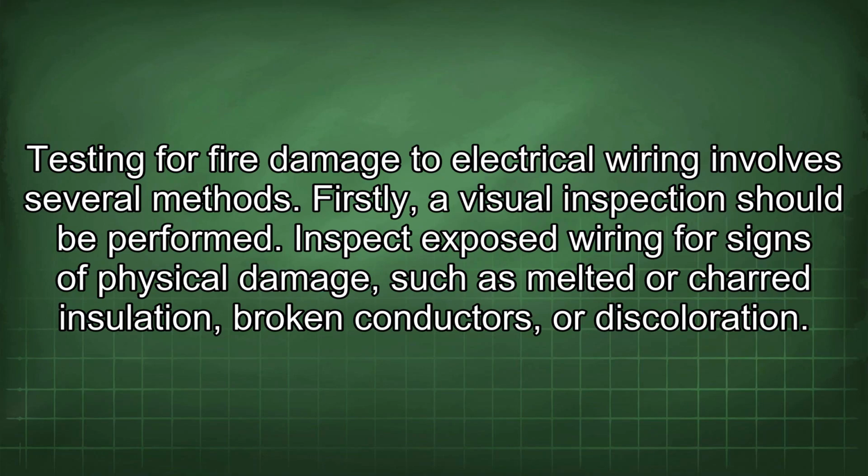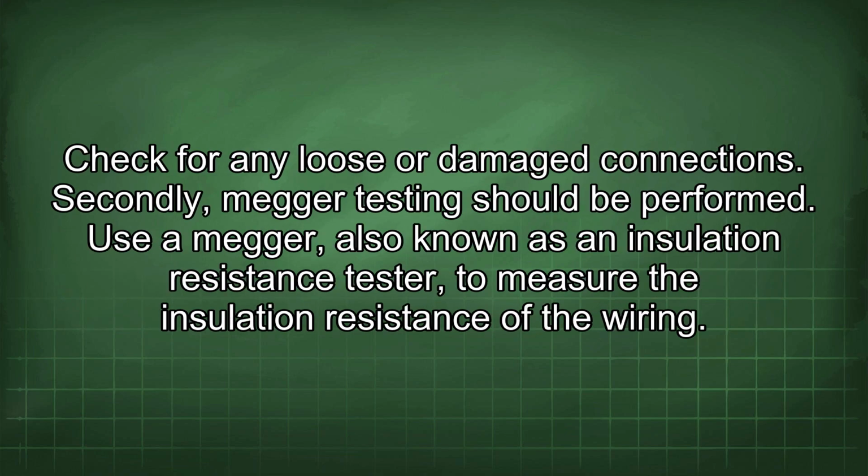Testing for fire damage to electrical wiring involves several methods. Firstly, a visual inspection should be performed. Inspect exposed wiring for signs of physical damage, such as melted or charred insulation, broken conductors, or discoloration. Check for any loose or damaged connections.